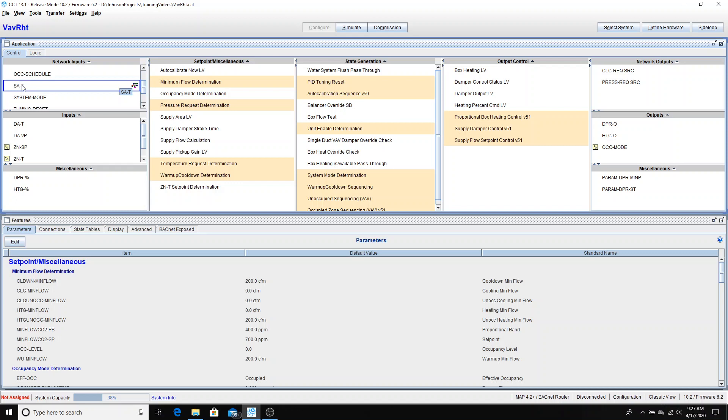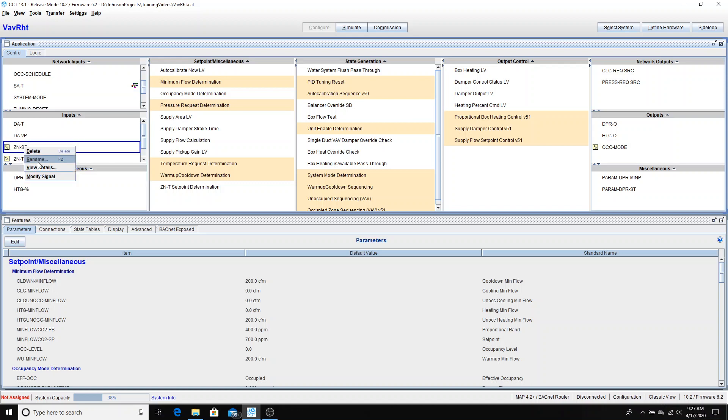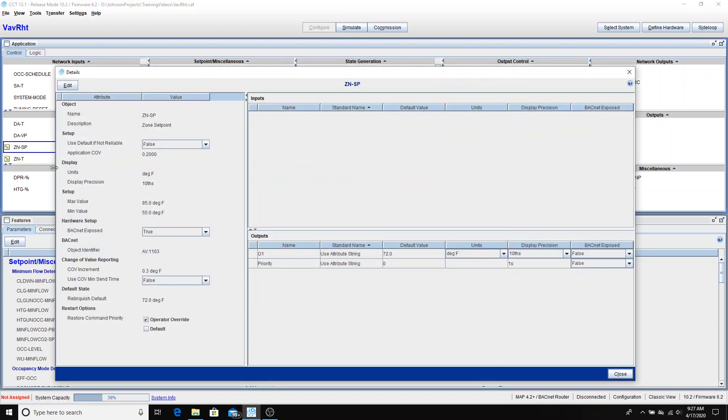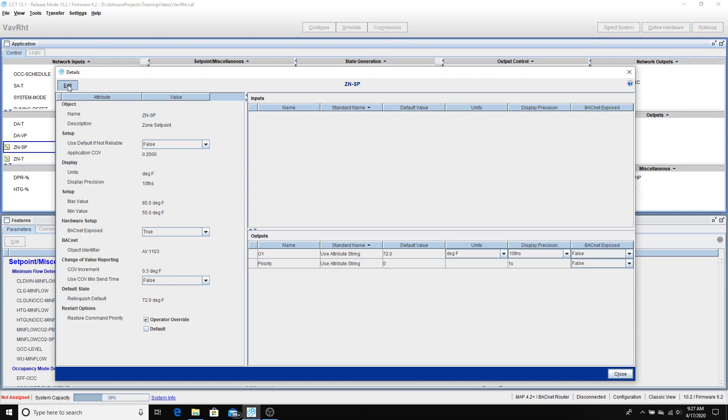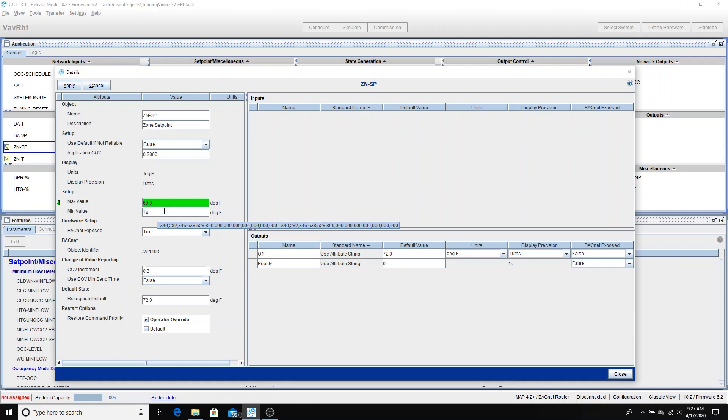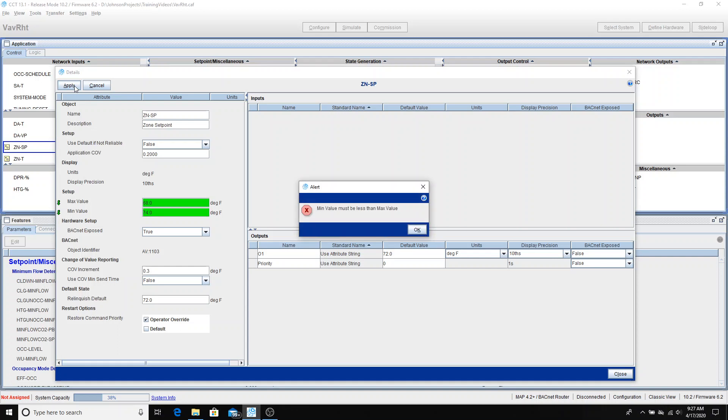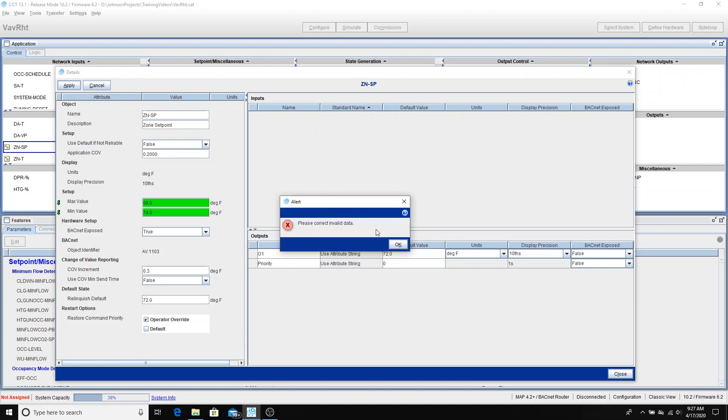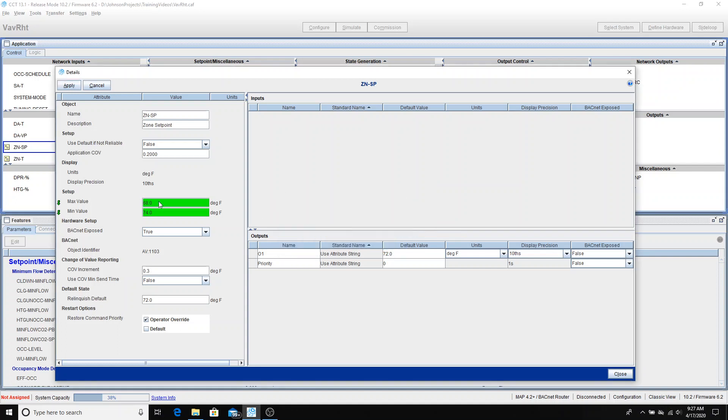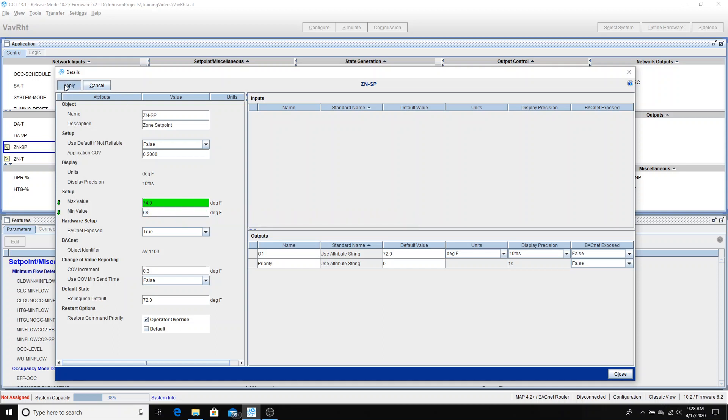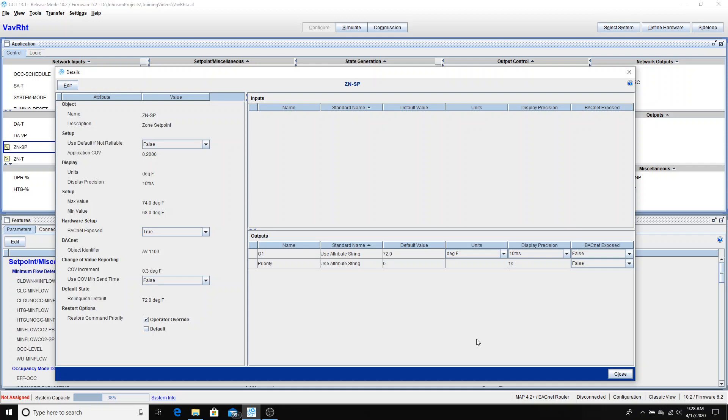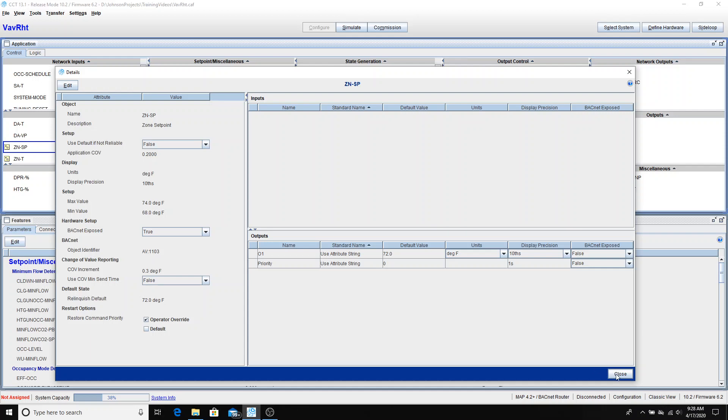Next thing that we need to do for our zone set point, I'd like to limit this so that people are not able to turn the set point knob all the way up or all the way down. So I want to give them adjustability, but not too much. So we'll go into the zone set point. I'll go into edit mode. And for this, I'm going to say they can go from 68 to 74 degrees. That'll give them a few degrees of adjustability. I guess I did that backwards. Max value, 74 min value, 68. Apply. And close.